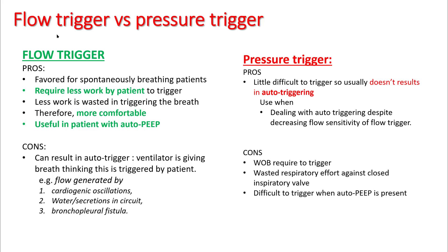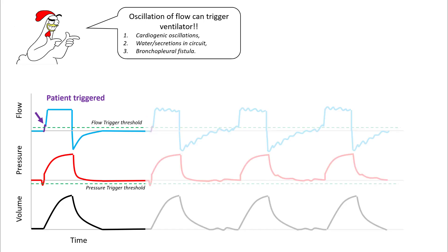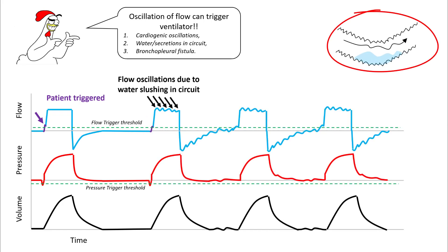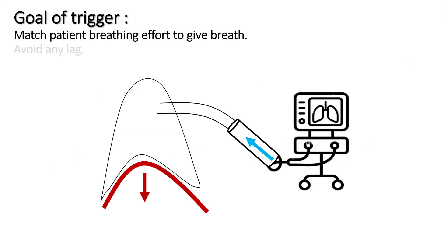Oscillation of flow can also trigger the ventilator. For example, if you have water slushing in the circuit, that creates turbulence and an irregular flow in the circuit, and if this is high enough, it can trigger a breath. The goal of the trigger is to match the patient's breathing effort — every time the patient wants to breathe, the machine has to initiate a breath.